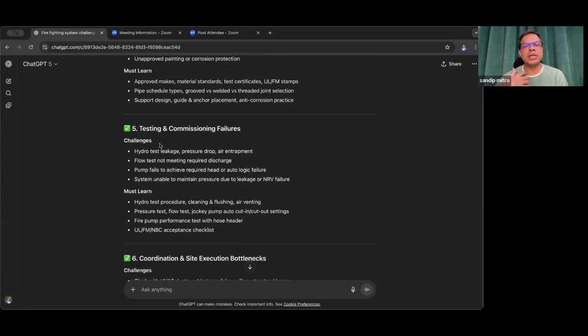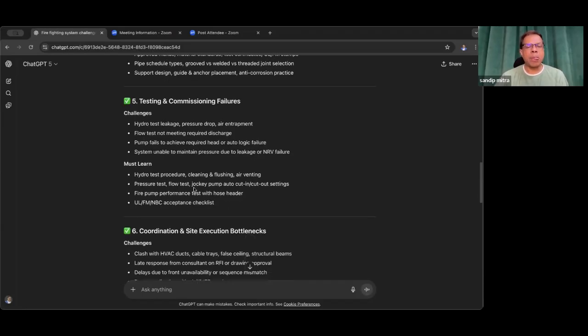And testing and commissioning failures. What are the failures? Hydro test leakage, pressure drop, air entrapment, then flow test not meeting required discharge, pump fails to achieve required head, auto logic failure, system unable to maintain pressure due to leakage or NRV failure. Now what you must learn from there: the hydro test procedure, flow test, jockey pump, auto cut in and auto cut out setting, fire pump performance test with the hose header, and UL/FM NBC acceptance checklist.